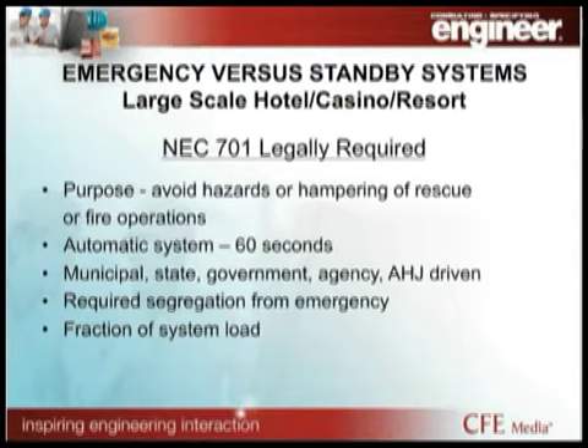When we talk about 701, the purpose of 701, we need to avoid hazards or hampering of rescue or fire operations in the event of a power outage. These are also automatic systems, but now we have 60 seconds, which is really good because it lets us stagger some of the big loads that make up this system from your lighting and your alarm systems and those systems that are really all about preserving life. It's driven by municipal, state government, and then also the AHJ. The AHJ in a specific jurisdiction.